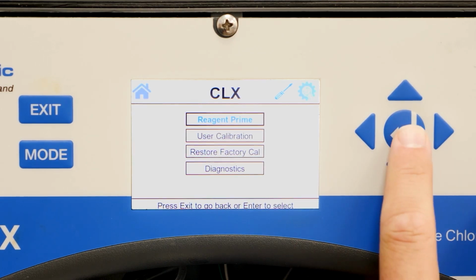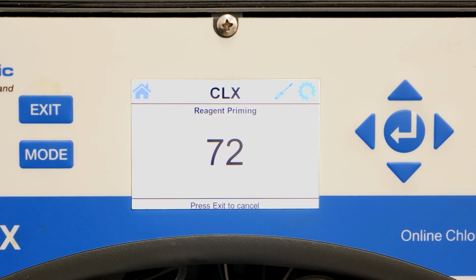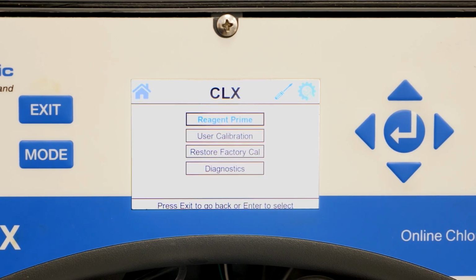By pressing enter on the reagent prime button, the analyzer will automatically begin the priming process. Be sure to flush the reagent tubing with DI water and the syringe provided with the analyzer before priming the reagents. The reagent pump will fire 75 times. You will need to hit exit when you are done priming to put the analyzer back into normal operation. Please refer to our reagent change video for more information on how to prime the reagents.